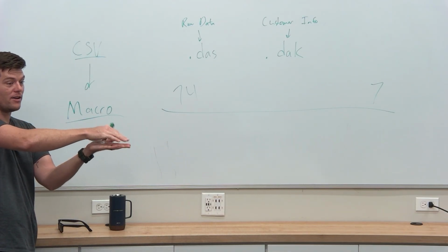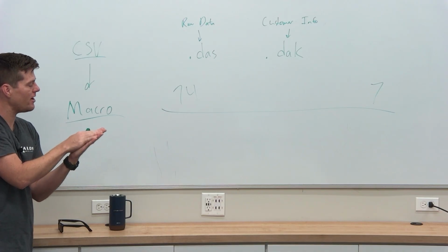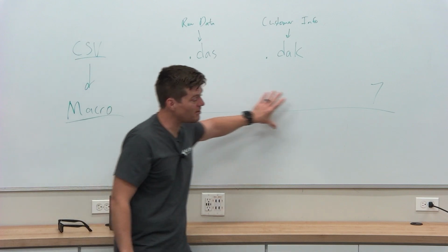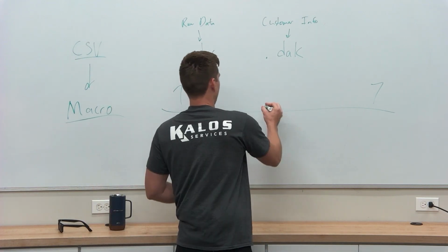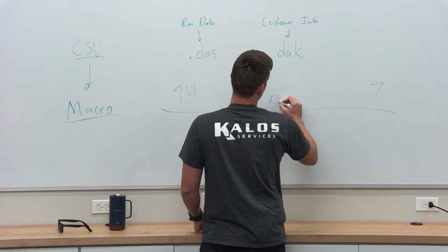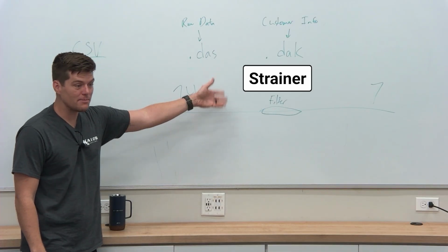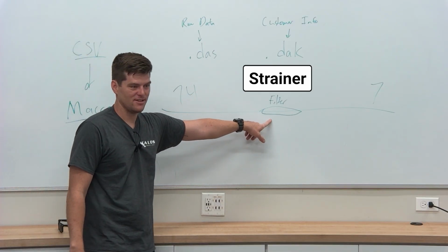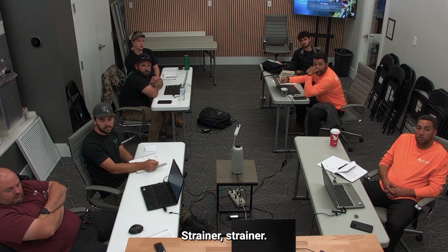And you can click a button and the numbers change. And as I see the numbers change, I can actually look at the diagram and say, well, these pipes are connected and there's nothing in between here, right? Except for, let's say there's a nice little refrigerant filter, right? And I would say, well, okay, from here to here, the only thing that's in between them is this. It's probably plugged. A strainer? Yeah, a strainer. Yep. Not a filter. I don't know why I use that terminology. But that's what the macro is designed to do.